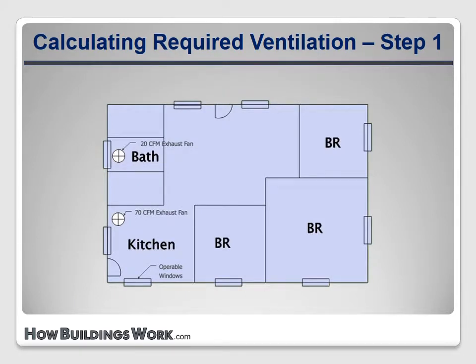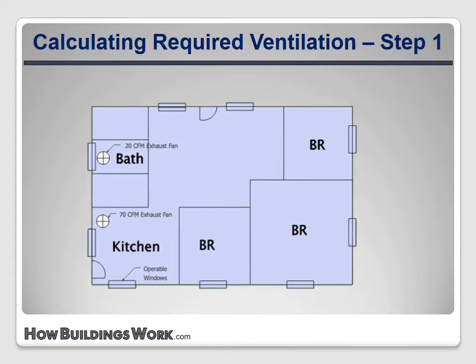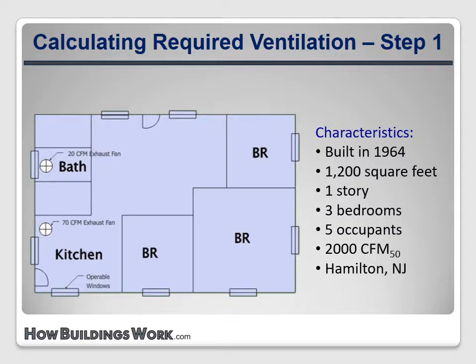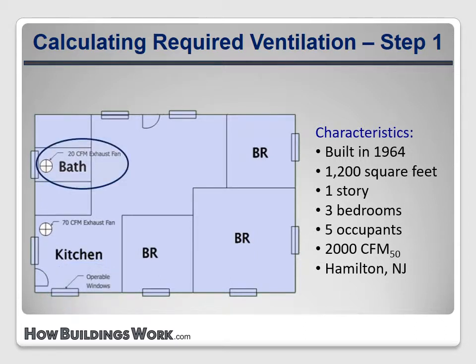Let's apply these calculations to an example house. We'll use the same floor plan and location as the new construction example, but change some assumptions. Based on a customer interview, the house was built in the 1960s and is occupied by a couple with three children — five occupants. The blower door reading is fairly high at 2000 CFM at 50 pascals. There are operable windows in the kitchen and bathroom; the bathroom has an exhaust fan measuring 20 CFM, and the kitchen has a sidewall vent fan measuring 70 CFM.